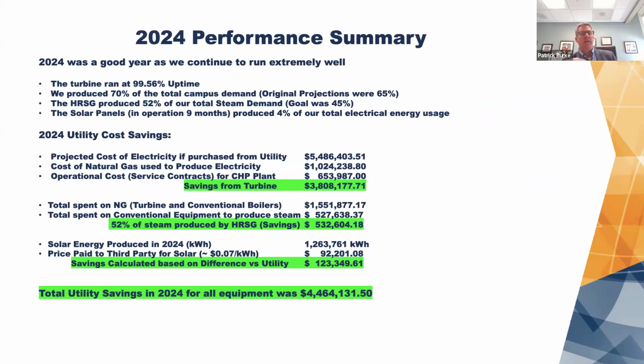Okay, so how did it all work? In 2024, the turbine was up over 99% of the time. We produced 70% of the campus demand. The original projections were 65%, so we've exceeded those original targets. The HRSG produced 52% of our total steam demand, versus a goal of 45%, which is huge because that saves us money and puts the CHP plant in kind of a sweet spot in terms of maximizing your return on investment, being able to use that hot air to make steam and to use all of the steam that you can produce.